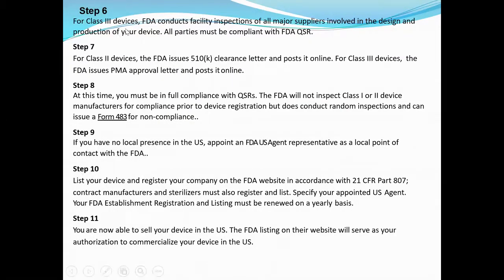The next step, for class 3 devices, FDA conducts facility inspection for all major suppliers involved in the design and production of your device. All parties must be compliant with FDA's QSR. Obviously, when it is the highest risk device, FDA will conduct the facility inspection. They will come and see whether your quality management system is robust, and whether you manufacture by following all the 21 CFR 820 parts or not. Just as we conduct the GMP inspection by FDA for drug products, similarly here also FDA comes to inspect your facility and check your quality management system as per 21 CFR Part 820.